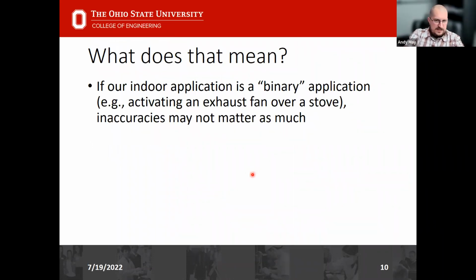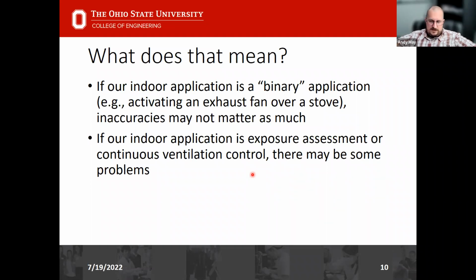And what does that mean? The quick take is that if we have a binary application, like activating an exhaust fan over a stove, accuracy may not matter as much. If we're just using the sensor as an on-off switch for localized particle control technology, maybe the inaccuracies don't matter as much. But if we're thinking about something like exposure assessment or continuous ventilation control, there may be some problems. If our sensors are inaccurate, we're obviously going to have some inaccuracies in our exposure assessment. And if we're using these to control ventilation for an entire building, we may be running our fans when we don't need to, or not running our fans when we do need to.